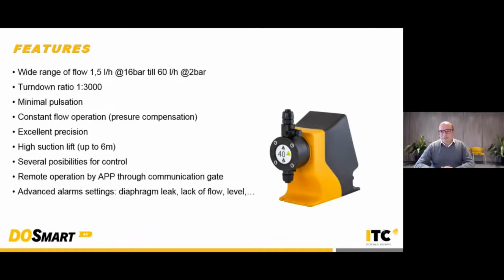What are the main features of this pump? It has a very wide range of flow, from 1.5 liters per hour at 16 bar till 60 liters per hour at 2 bar. The turn-down ratio we can achieve with this pump is extremely important. We can reduce the flow up to 3,000 times. Remember that under normal operation, a DOStech pump can be regulated from 10 to 100%. So the turn-down ratio is from 1 to 10. We are going to 3,000. This allows us to dose even in the range of milliliters per hour.